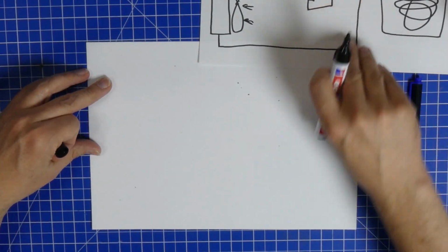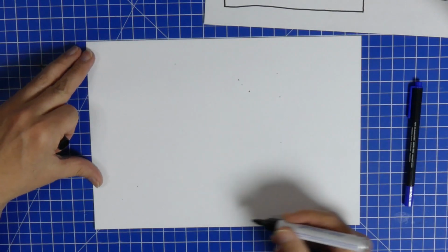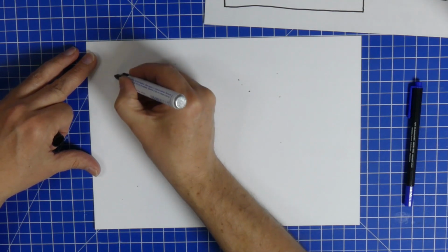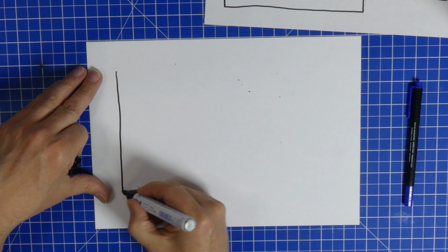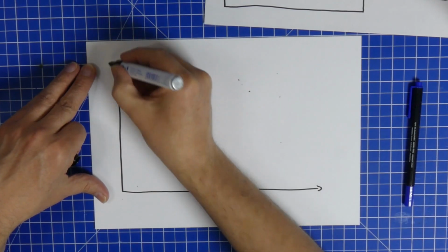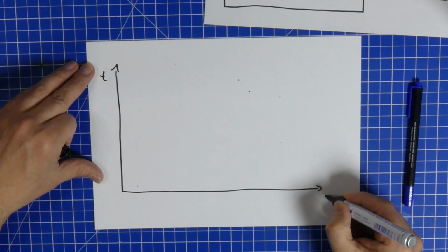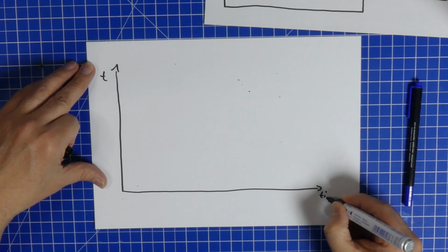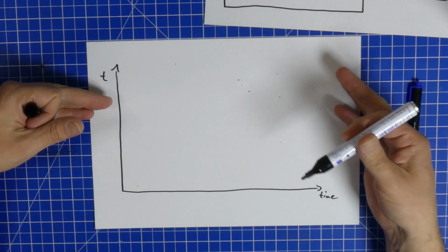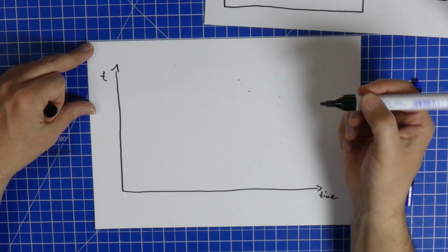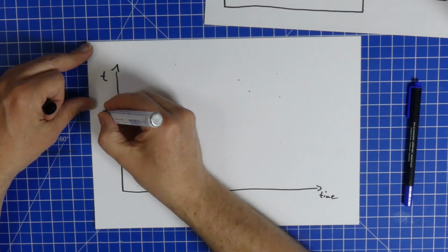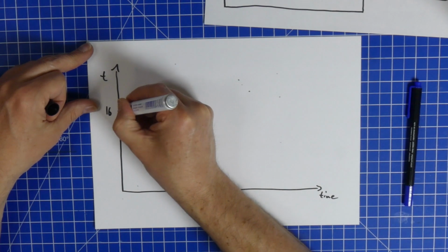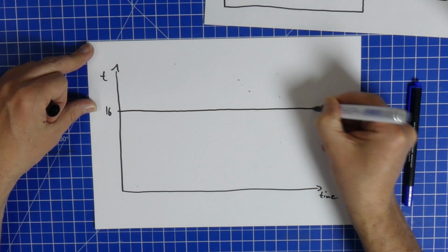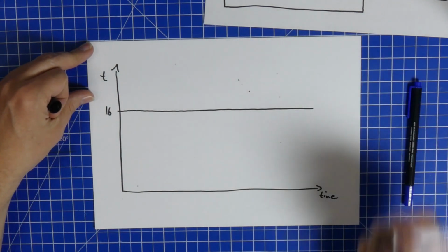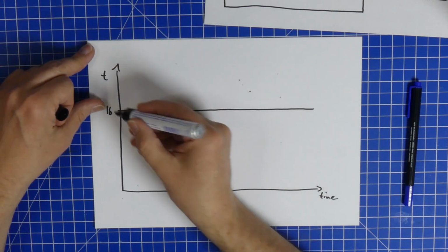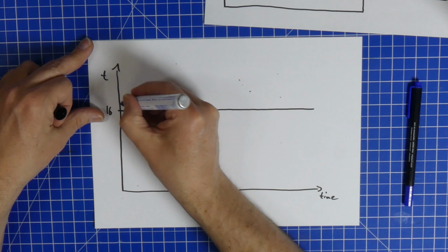Now, suppose we have the temperature on our y-axis, and we've got time on our x-axis. So this here is temp, and this here, that's stupid, this here is time. And we have several set points. For example, there is a temperature that we can set. For example, we want to set 16 degrees as the temperature where we want our cooling to turn on. There is something called the hysteresis, which is a second value that gets added to that 16, which is slightly above that.